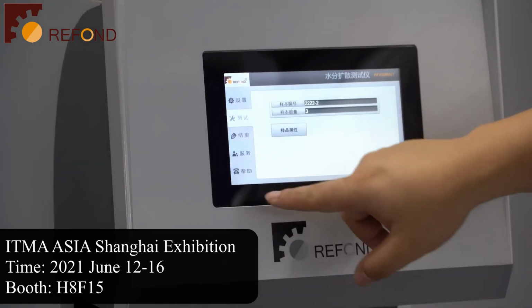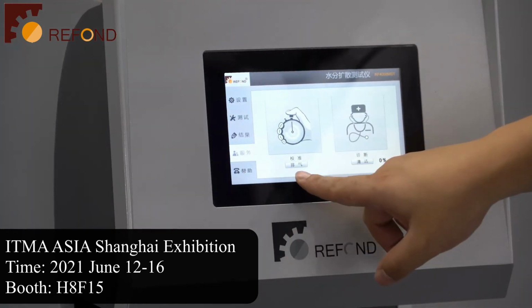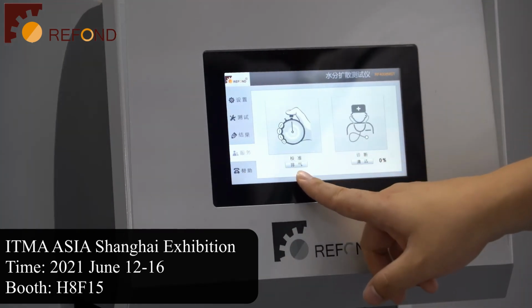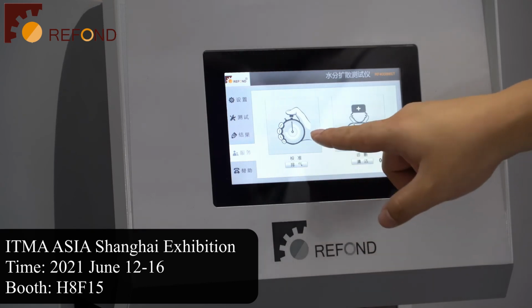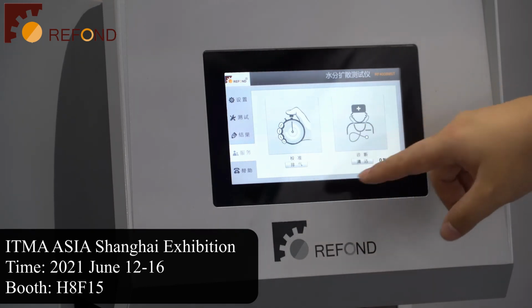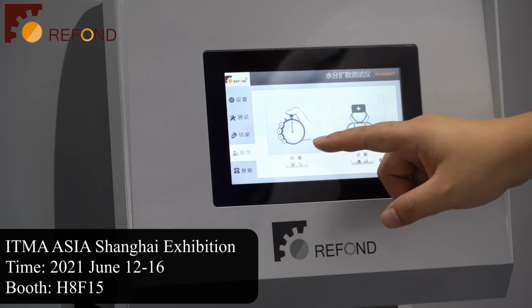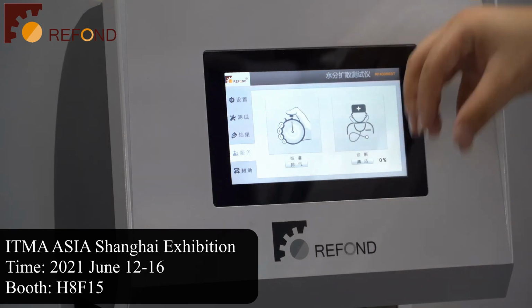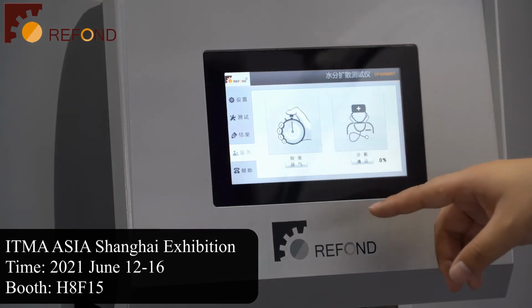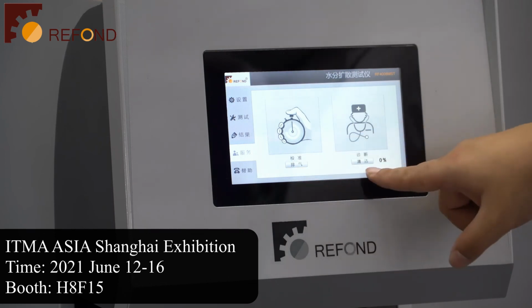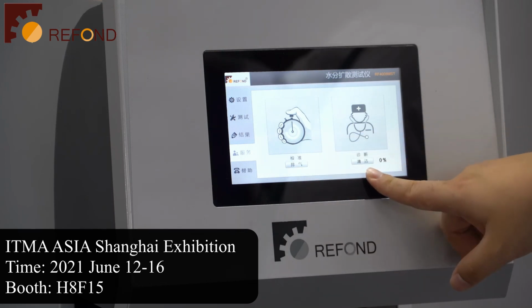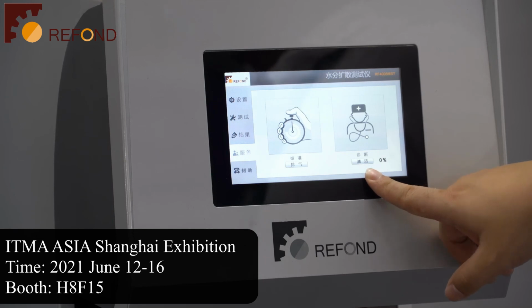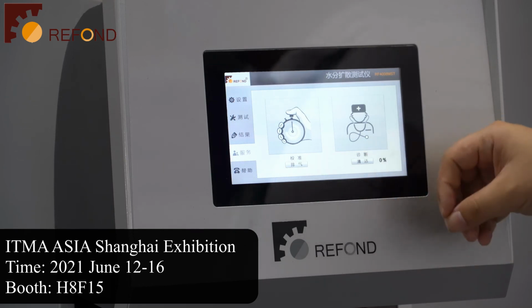In the service page, there's a button for purging the air inside the pipeline, a calibration page, and a diagnose page. In the calibration page, you will be able to calibrate the loading force and also the pumping liquid amount. This button here is for cleaning of the top and bottom probe, the cleaning function that we just talked about.